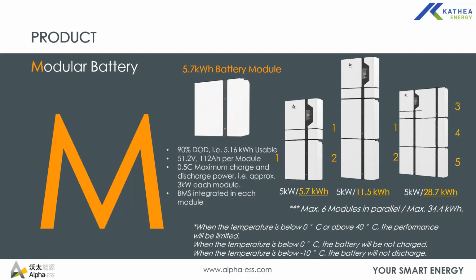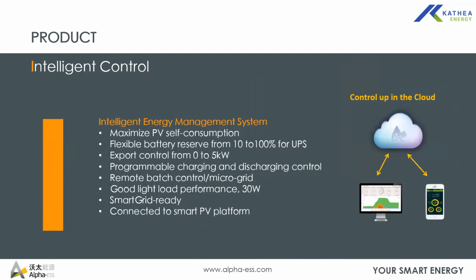The operating temperature range is suitable for our region. It operates from 0 to 40, which is the nominal temperature. However, if push comes to shove, it can go up to 60, but we recommend keeping the environment within 40 degrees. If temperatures can go beyond that, there will be need to put in an air conditioner to maintain the temperature below 40 for optimal operation.